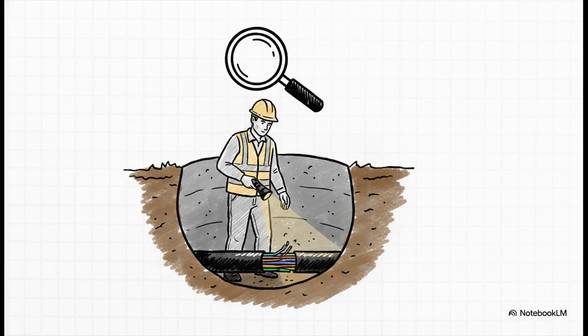Now, why those specific numbers? Well, it's actually a brilliant piece of practical engineering logic. A 1 meter square hole that goes 1.5 meters down gives a human worker just enough physical space to safely get down into the earth, dig with hand tools, and visually confirm the exact depth and position of the cable. But at the same time, it's narrow enough to be practical, meaning you can dig repeatedly along a cable route without requiring excessive, back-breaking labor. It really hits the perfect balance of human safety and physical verification.